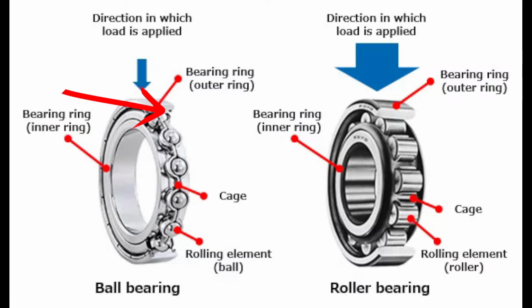So in that particular case, I just use a little small screwdriver. It doesn't take much, but you'll just pop one shield out. You'll try to get underneath the shield, in between the shield and the race, and just kind of ping it out. Remove one side, leave the other, and then the shielded side is going to be in towards your motor and your stator and the rotor, right? And then the non-shielded side is typically going to be your outer side, and that's where the grease is going to come in from the grease housing.